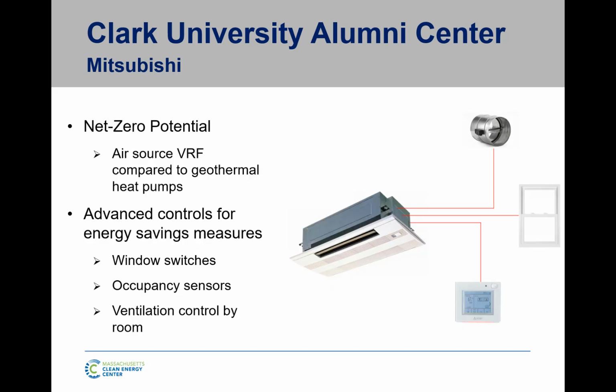So one of the unique things done here was, first, they compared the air source VRF to geothermal heat pumps, mostly by doing an eQuest energy study on the entire project. One of the really cool things with this was it was monitored after the fact, because at the time it was a National Grid incentive that they were going for, that had to compare actual performance to modeled performance. And it was within a few percent of the modeled performance. So the person who did the energy model was very happy that their predicted energy use and actual energy use were very close, much closer than expected. It was like a couple percent.